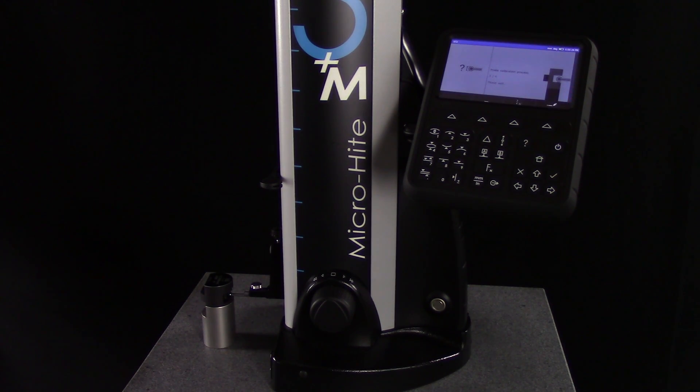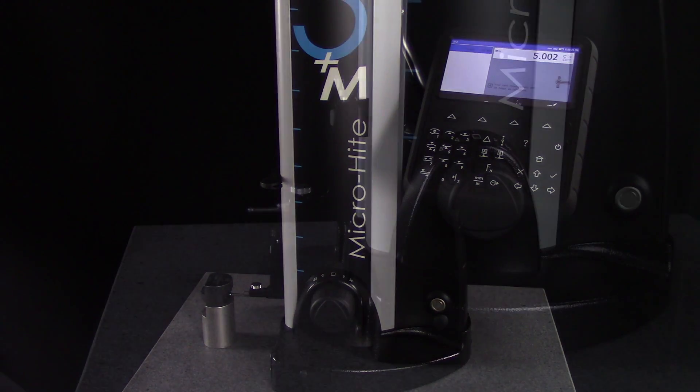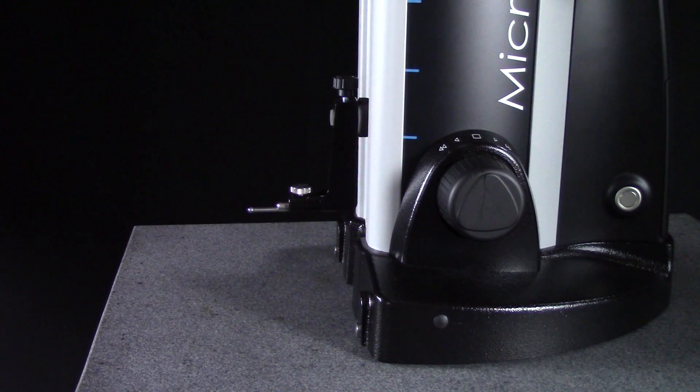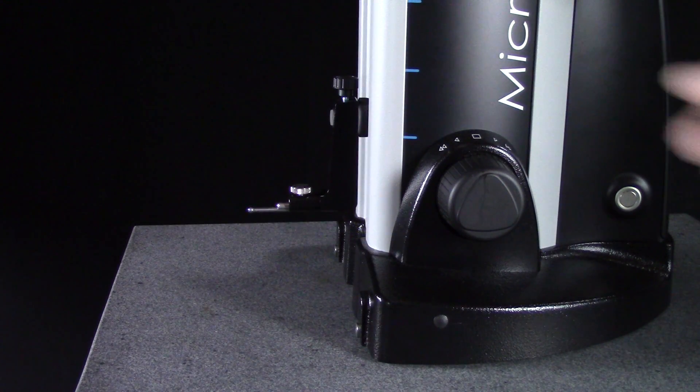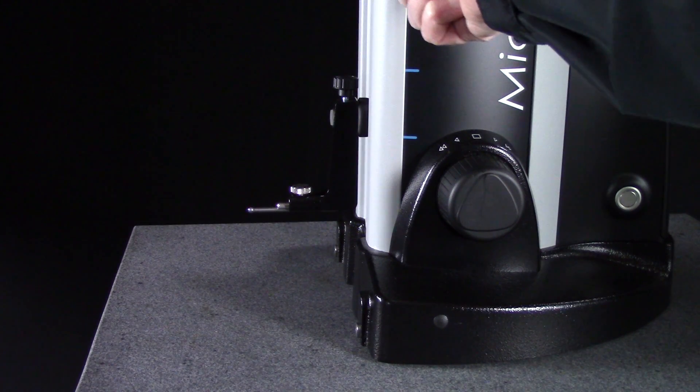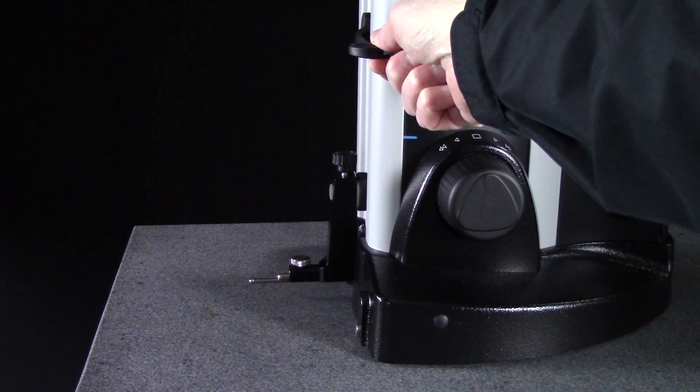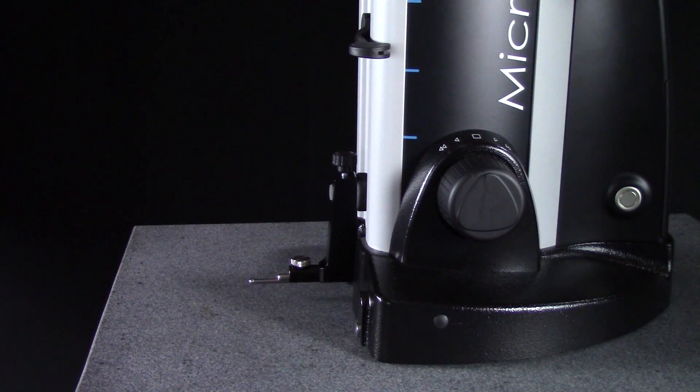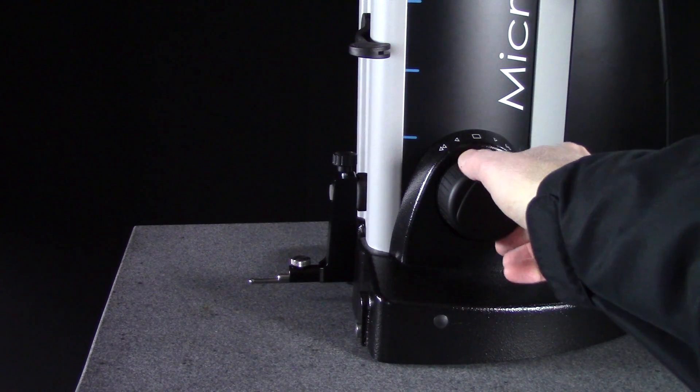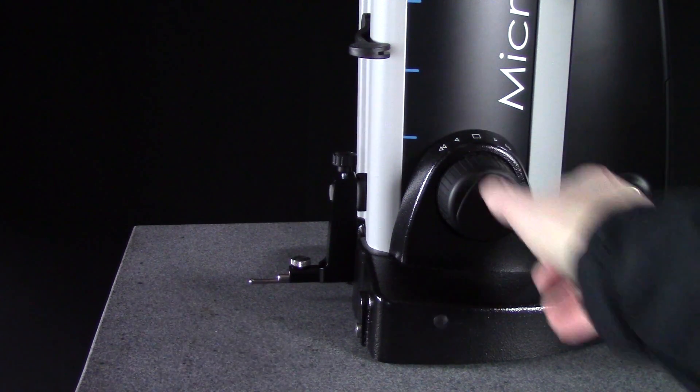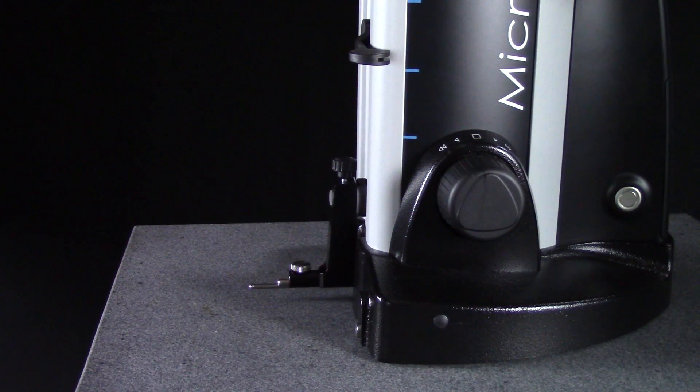Once the gauge is calibrated, you're ready to establish your datum point and begin measuring. I'll set my datum to the surface plate by turning the rotary control handle counter-clockwise and moving the probe downward.